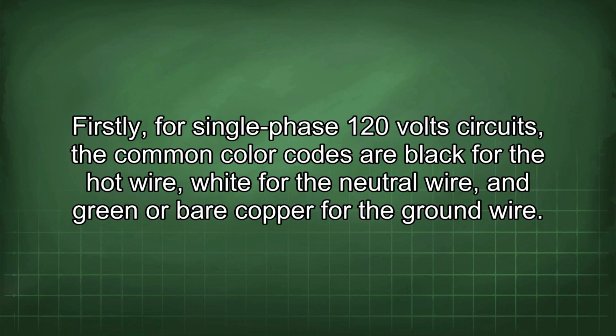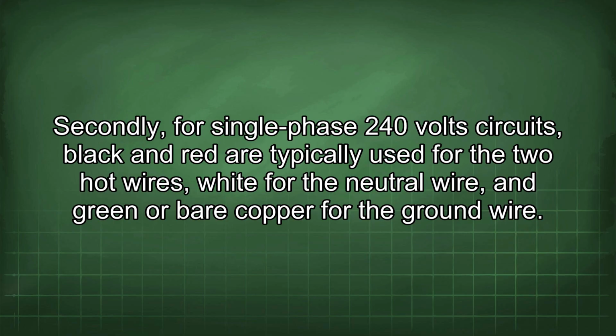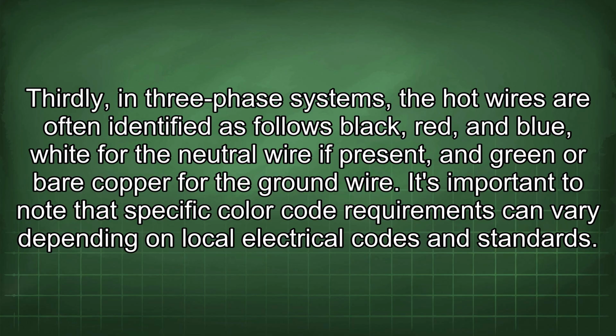Firstly, for single-phase 120-volt circuits, the common color codes are black for the hot wire, white for the neutral wire, and green or bare copper for the ground wire. Secondly, for single-phase 240-volt circuits, black and red are typically used for the two hot wires, white for the neutral wire, and green or bare copper for the ground wire. Thirdly, in three-phase systems, the hot wires are often identified as black, red and blue, white for the neutral wire if present, and green or bare copper for the ground wire.